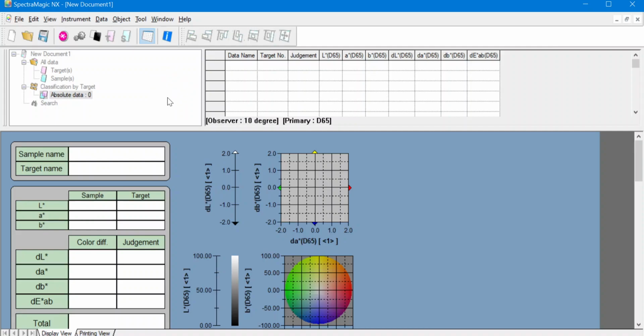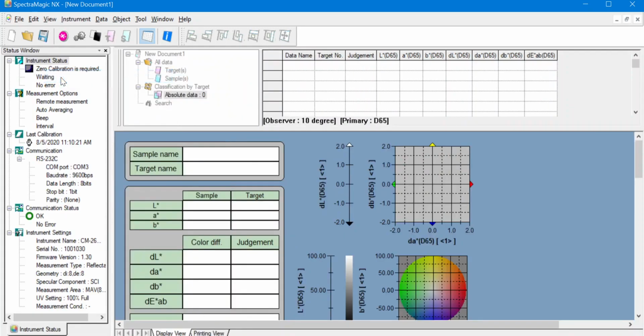It will take a while to establish the connection. However, once you establish the connection, you may have a status window over here. If you have established the connection correctly, it would say 0 calibration required or white calibration required. On the bottom right of the screen, you will see the model. I have my model CM-2600d connected over here. If it's not connected, on the status bar it would say here not connected, and here would say none at the bottom over here. So I'll re-establish the connection again.